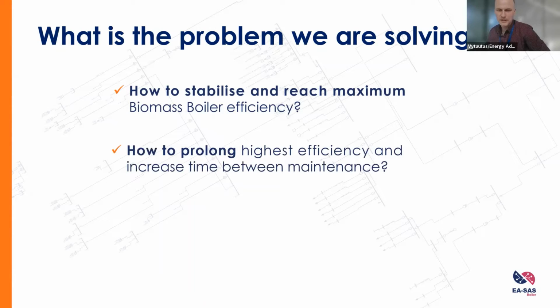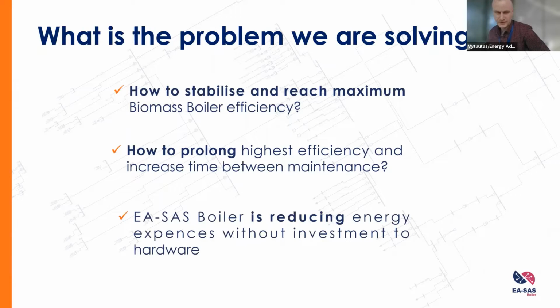The next question is how to prolong highest efficiency operation and then increase time between maintenance. It's absolutely related to the first: if you stabilize, we prolong efficiency. We use a digital twin in a SaaS platform to reduce energy expenses, in fact without investment in hardware. When our partners come to the boiler, first we connect to SCADA, PLC or OPC, collect the data online, do an inventory, and tune set points like advanced process control to optimize operation. So we can achieve some percentage of fuel consumption reduction only by tuning set points, without hardware investment.